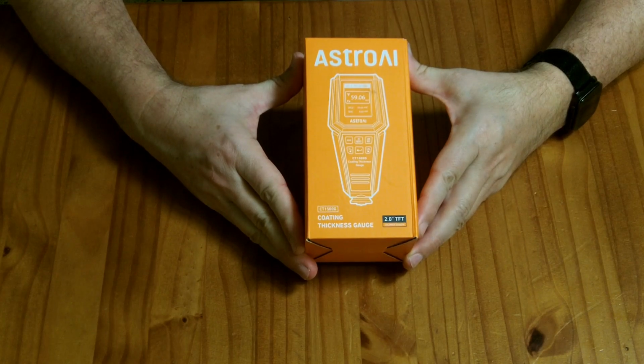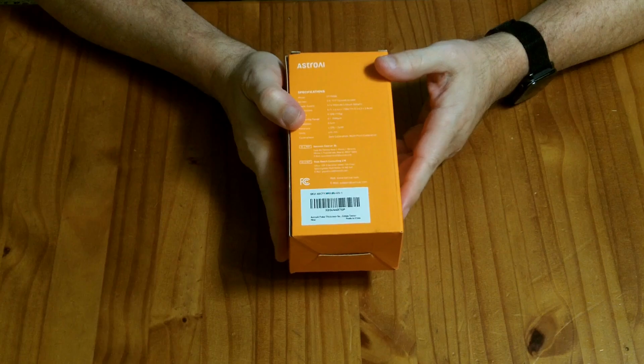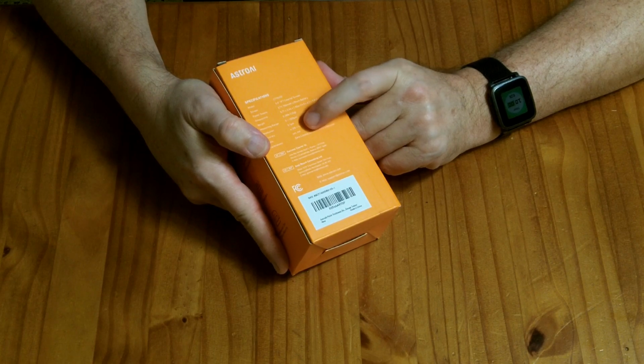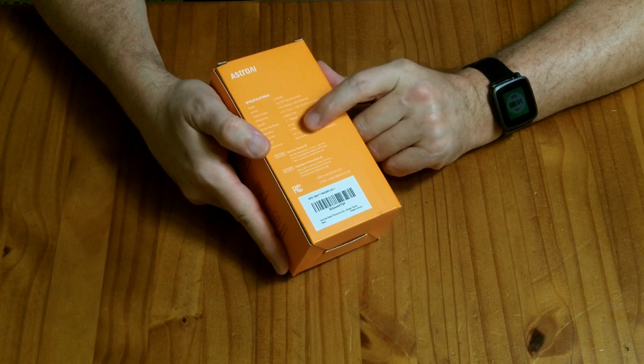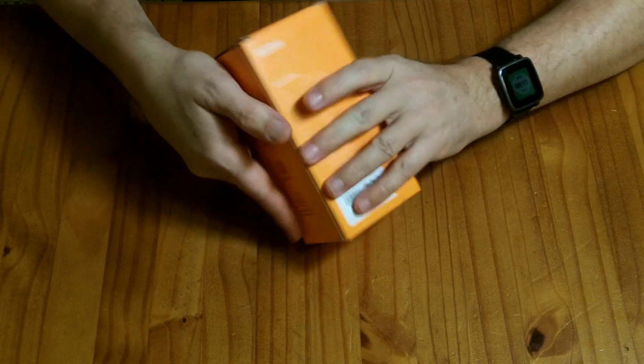This is a coating thickness gauge, and according to the specifications here, it can read in micrometers 0 to 1500 micrometers, and its resolution is 0.1 micrometers, and its accuracy is 3% plus or minus plus 2 micrometers.